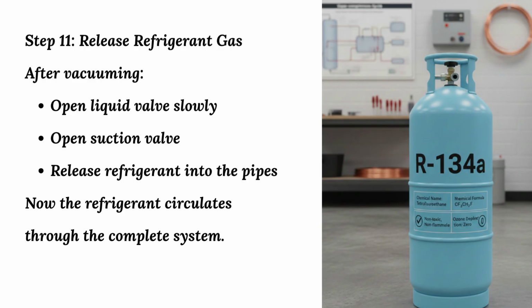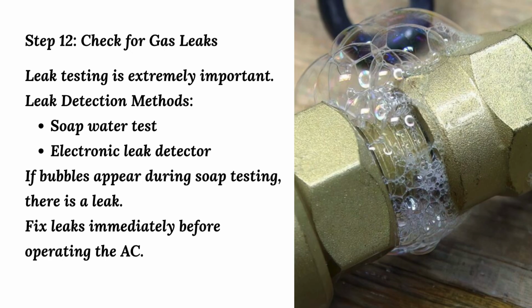Step 11. Release refrigerant gas. After vacuuming, open liquid valve slowly. Open suction valve. Release refrigerant into the pipes. Now the refrigerant circulates through the complete system. Step 12. Check for gas leaks. Leak testing is extremely important. Leak detection methods: soap water test, electronic leak detector. If bubbles appear during soap testing, there is a leak. Fix leaks immediately before operating the AC.